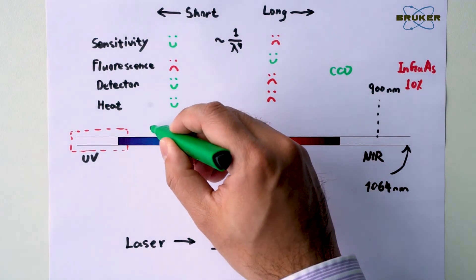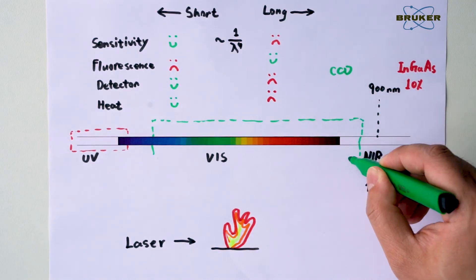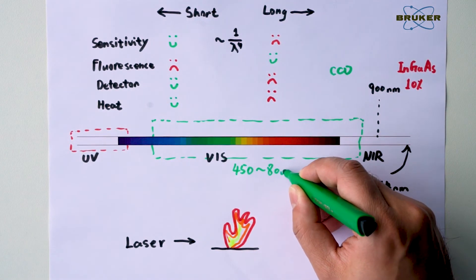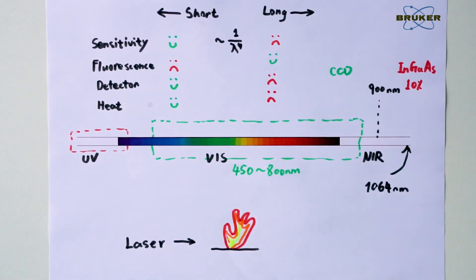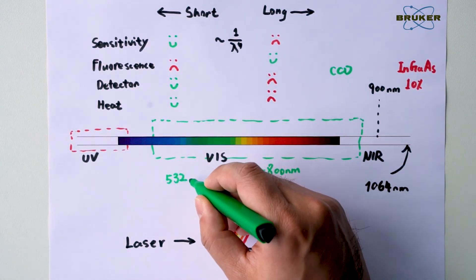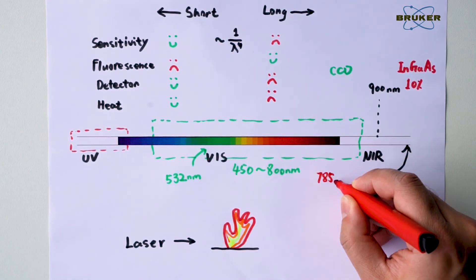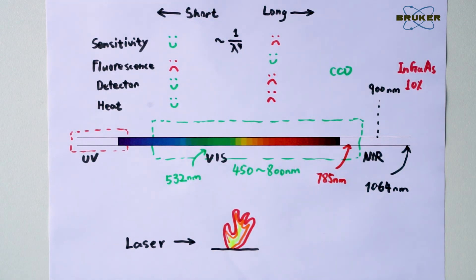Consequently, considering all these factors, most regular Raman measurements use lasers in range of 450 nm to 800 nm. And the two most widely used are 532 nm green laser and 785 nm infrared laser.